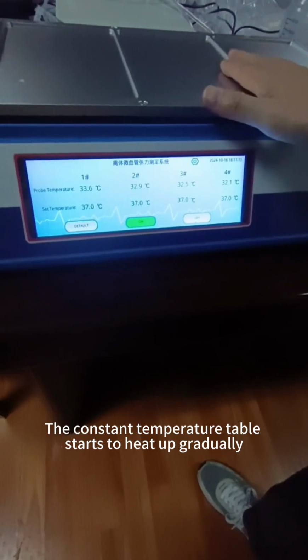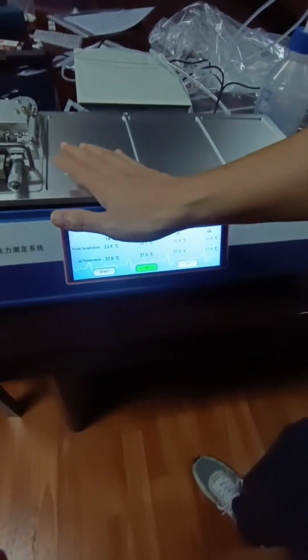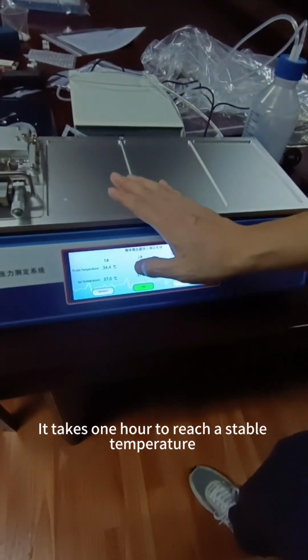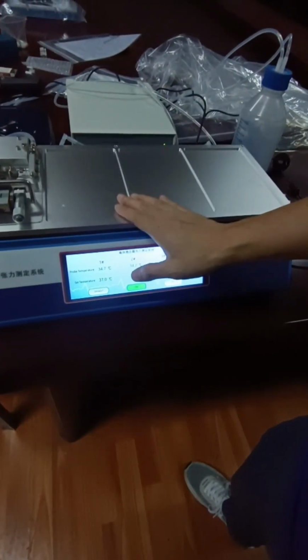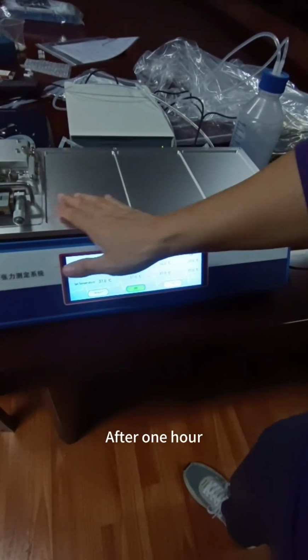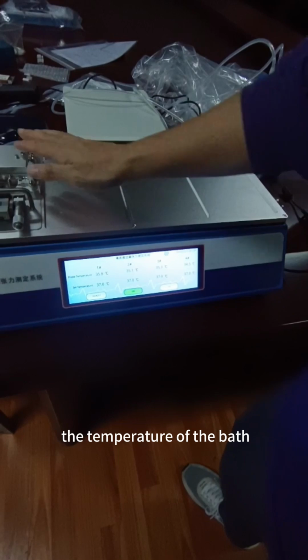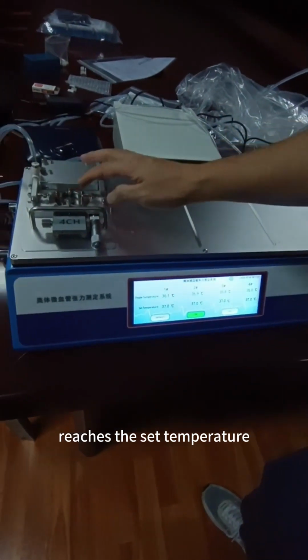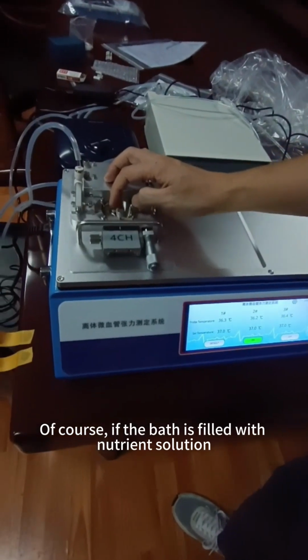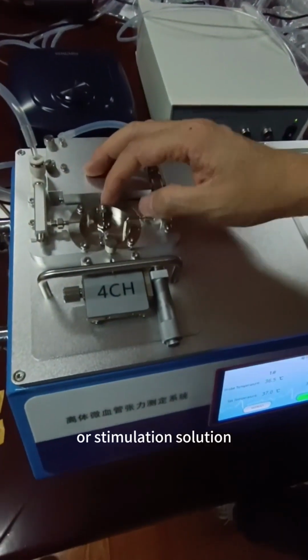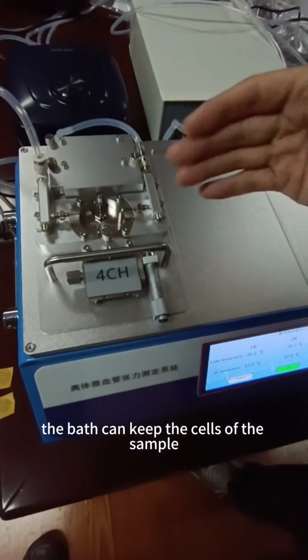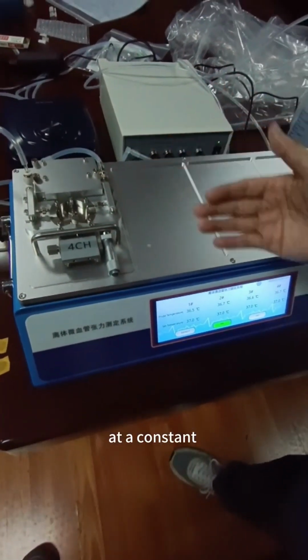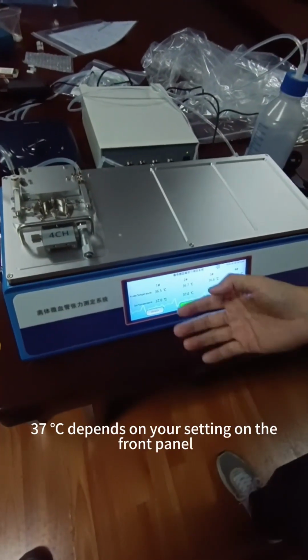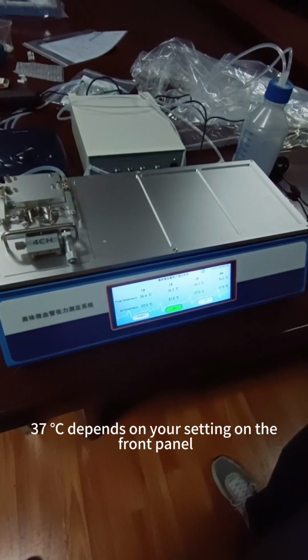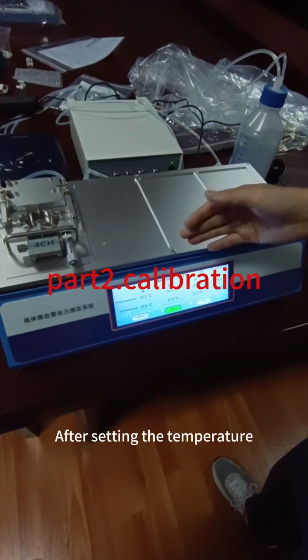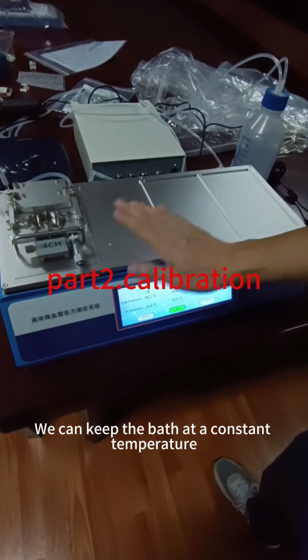The constant temperature table starts to heat up gradually. Generally speaking, it takes 1 hour to reach a stable temperature. After 1 hour, when the temperature of the thermostat is balanced, the temperature of the bath reaches the set temperature. Of course, if the bath is filled with nutrient solution or stimulation solution, the bath can keep the cells of the sample at a constant 37 degrees Celsius. The 37 degrees Celsius here depends on your setting on the front panel. After setting the temperature, we can keep the bath at a constant temperature.